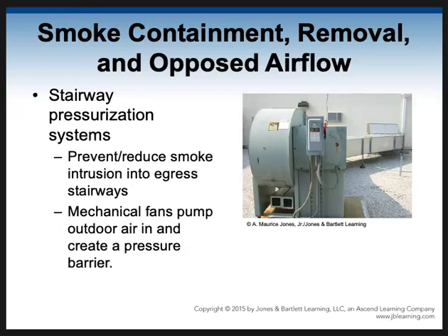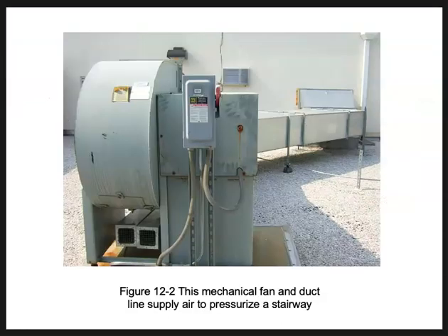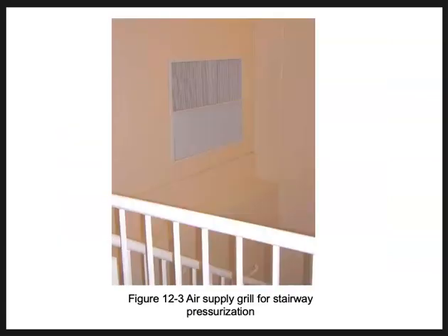It prevents or reduces smoke intrusion into those egress stairways. These mechanical fans pump the outdoor fresh air in and create a pressure barrier. So here's a close-up of that fan and the ductwork that's going in, and on the other side of that wall, here's the grill where that air is being pushed into this stairwell.